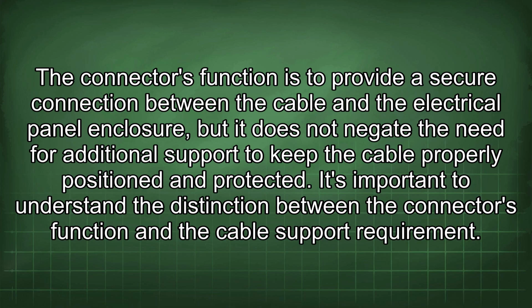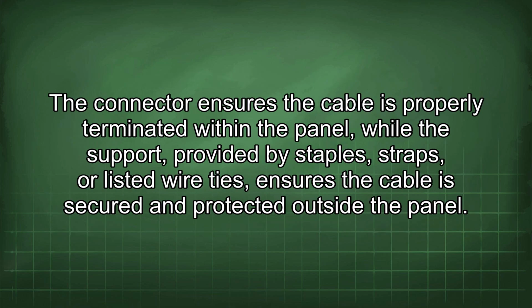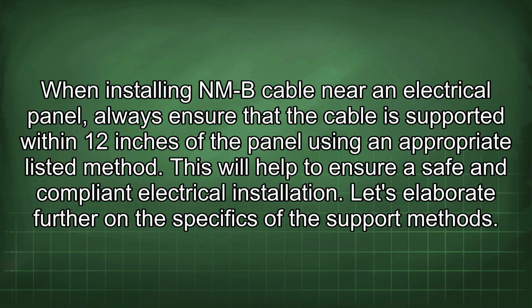It's important to understand the distinction between the connector's function and the cable support requirement. The connector ensures the cable is properly terminated within the panel, while the support, provided by staples, straps, or listed wire ties, ensures the cable is secured and protected outside the panel. When installing NMB cable near an electrical panel, always ensure that the cable is supported within 12 inches of the panel using an appropriate listed method. This will help to ensure a safe and compliant electrical installation. Let's elaborate further on the specifics of the support methods.